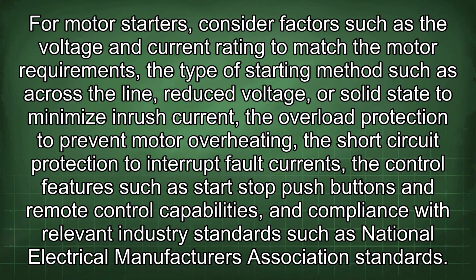For motor starters, consider factors such as the voltage and current rating to match the motor requirements, the type of starting method such as across the line, reduced voltage, or solid state to minimize inrush current, the overload protection to prevent motor overheating, the short circuit protection to interrupt fault currents, the control features such as start-stop push buttons and remote control capabilities, and compliance with relevant industry standards such as National Electrical Manufacturers Association standards.